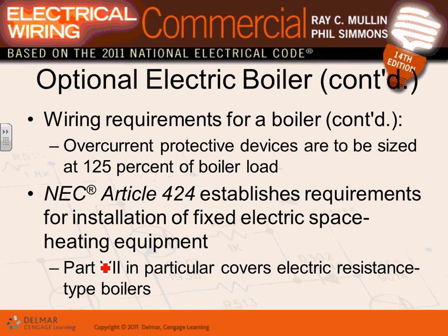Overcome friction device, we speak of the devil. There you go, 1.25. Which article talks about the fixed boiler, heating boiler? 424. Article 424, if you go there, it will tell you exactly 1.25 is that magic number. And anybody knows why 1.25, guys? Continuous load. So that's it.